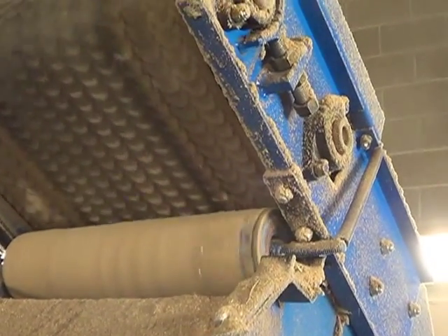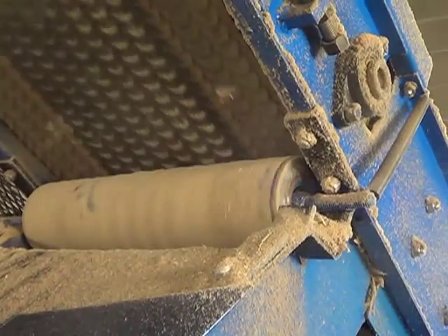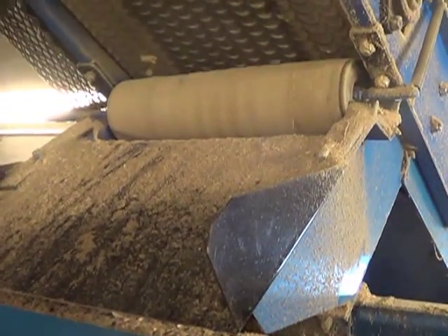And the little pieces — how does that work? The little pieces are dropping inside the device. The small chips. There's a bunch of them, and every now and then a big one. If it's too big to fit and the conveyor goes on the boiler, it separates it like this, and they just got a trash can here. And then you got these eyes that look in the window, tell us when it's full, and that starts and stops the conveyor. Ain't that cool?